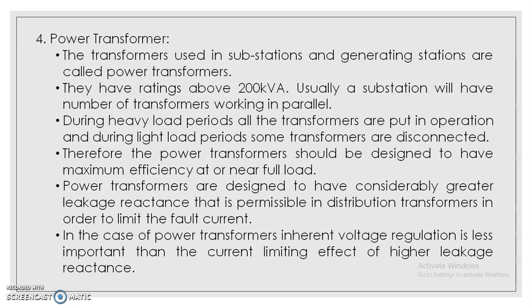Further, a good inherent voltage regulation is not very important in this case. Therefore, a higher leakage reactance is permitted, having an advantage of limiting the rush of current during short circuit or switching in the supply.